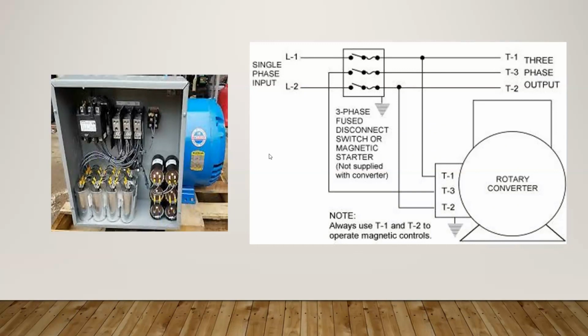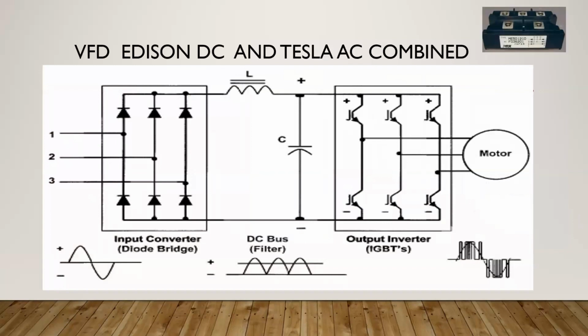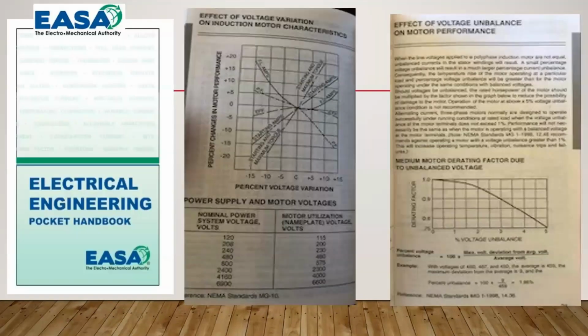The problem is that you've got inefficiency losses of running this rotary transformer. You've got some losses in your capacitor. Plus, again, you can't get the balanced phase angle. So the thing that you have to be really careful of when you run phase converters is how balanced all three phases are that it's creating. And typically on a standard phase converter, it's not very balanced. If you measure the voltage, line to line, the phase angles are never quite perfect.